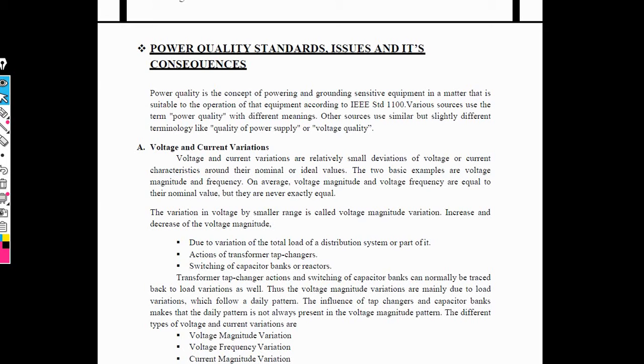That means this point is very important, in which we have to measure the power quality with the help of the IEEE standard. Then we also need to measure the power supply and check the quality of the power supply, and this power supply can be divided into two variations, that is voltage variation and current variation. That means in voltage variation we have to measure the deviations of voltage, and in current variation we have to measure the deviations of current at nominal values and ideal values.